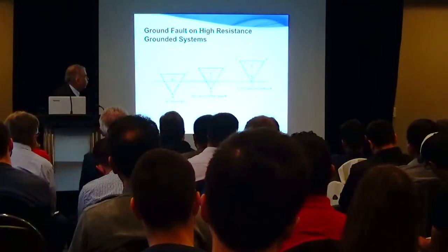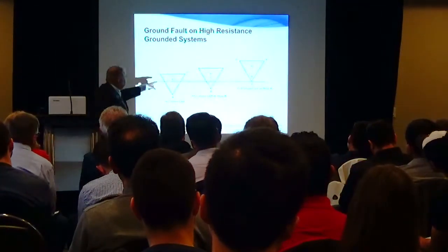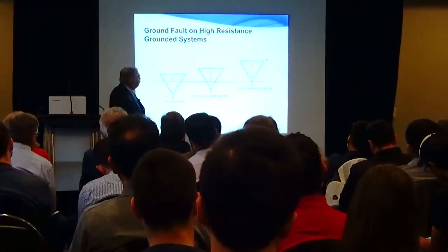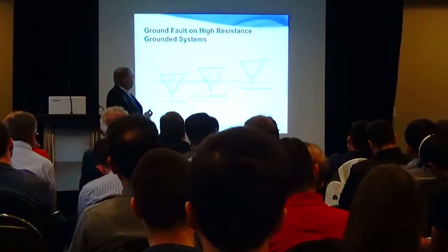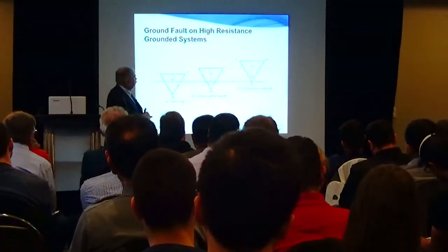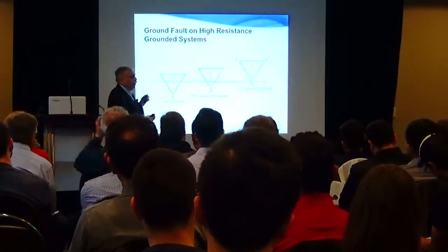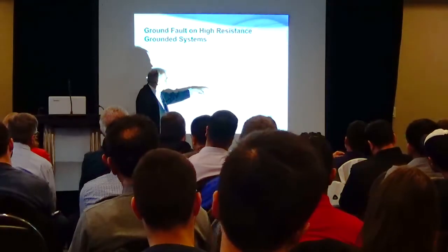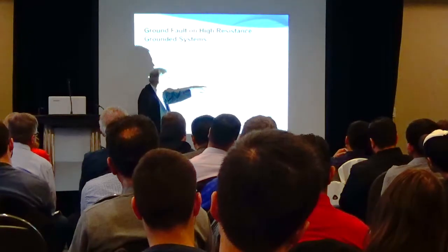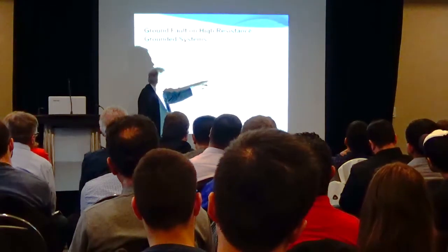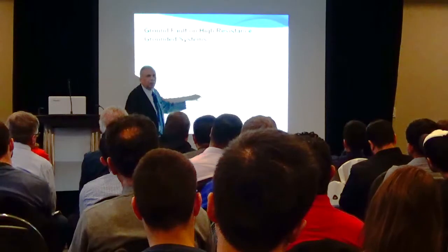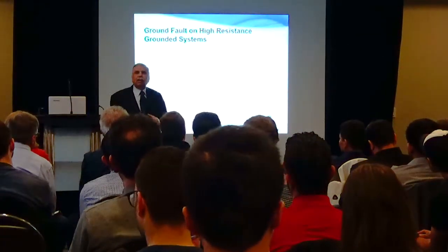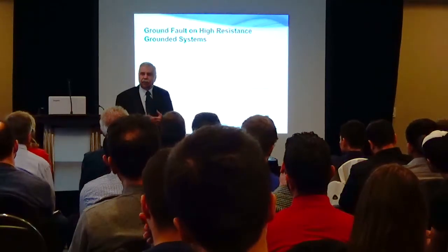Now what happens to the voltage? You heard the discussion. The neutral was sitting at the G point in the center of the triangle. As the insulation breakdown begins to appear, the balanced impedances to ground get affected. One impedance is lower. The G begins to shift towards the leaky phase. So now I have G to B less than G to C and G to A. And this can be tracked by voltage measurement. And you can get a systematic indication in advance of the fault.